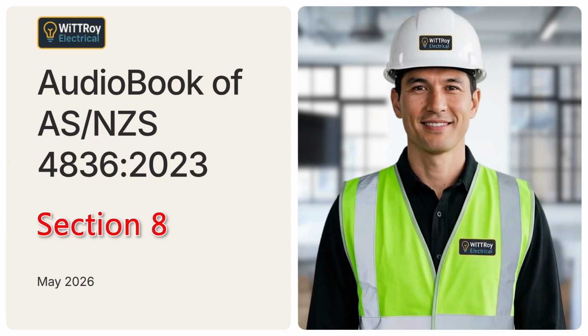That brings us to the end of Section 8 of AS/NZS 4836. This section reminds us that safety equipment and tools must be suitable, maintained, tested, inspected, and used correctly. Before using tools or safety equipment, check them. If they are defective, tag them and remove them from service. Use approved insulated tools. Prefer battery-powered tools where suitable. Use RCD or isolating transformer protection for portable electric tools where required.